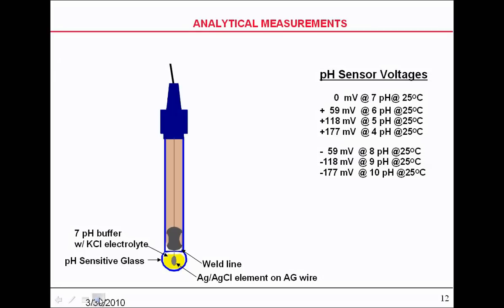It's important here to note that buffers have the same situation. If it's a 4 buffer, that is 4 or 4.1 or 4.2, whatever the side of the bottle says, at 25 degrees C.